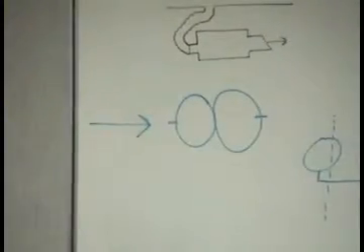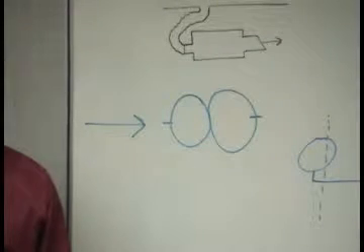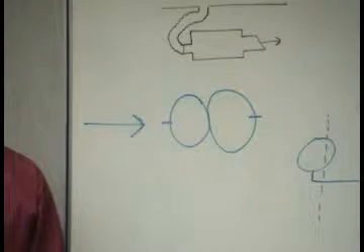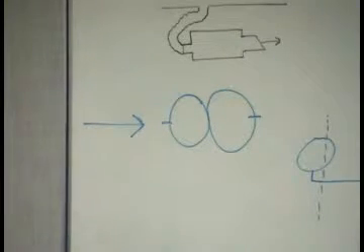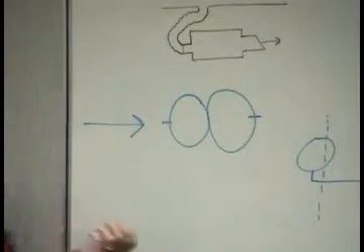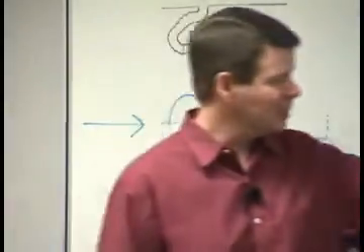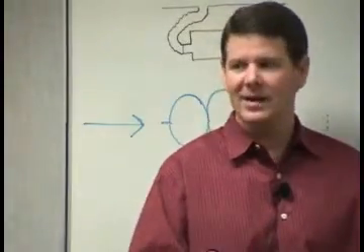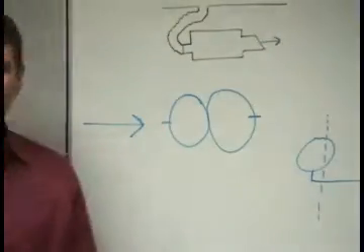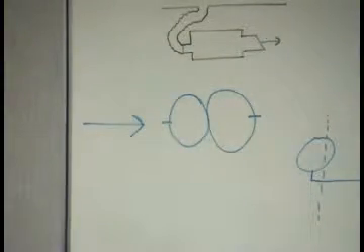And if, like Mick was saying, you have a great difference in temperature, you've about eliminated any possibility of it ever happening. The closer they are in temperature, the better off you're going to be. But somewhere in the middle, you come down to a point where you get more velocity out of there. And when you have more velocity through that hot water coil, it's also cooler, because we're not heating it as much. So it's kind of a double benefit.